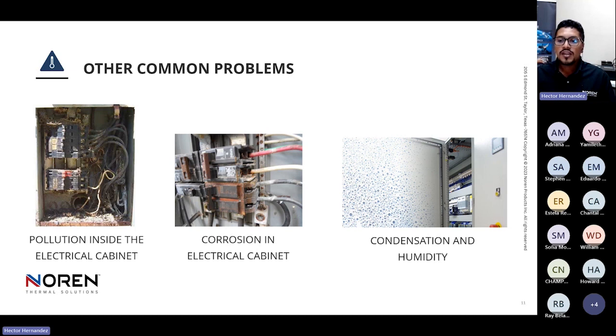Condensation and humidity. Humidity exists everywhere. However, there are some industries that are more exposed to humidity, like water treatment, again industry operating near the ocean, or industry where they have connected an air conditioner, because an air conditioner works by cooling the air inside the electrical panel. Even if we connect an air conditioner with too high a capacity, we can drop the temperature too much and reach the dew point. Then condensation will start appearing on our equipment. It can cause a short circuit, it can cause an emergency stop, and this is really expensive for all companies.